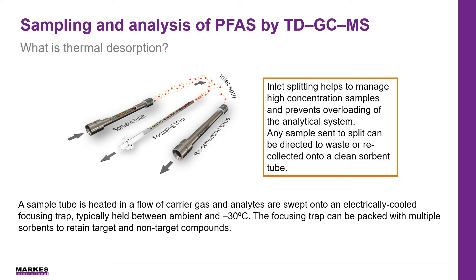For those of you unfamiliar with thermal desorption, let me quickly explain the process. Sample tubes are placed into the thermal desorber and leak checked prior to being heated in a flow of inert carrier gas. This releases the retained compounds and transfers them onto a narrow electrically cooled focusing trap. During this process a portion of the sample can be split and recollected onto a clean adsorbent tube, which can be used to store a precious sample, to validate the methodology, or to ensure efficiency of the method such as the complete desorption of the tube. This really is key to ensure good practice, validate the results and ensure robust methodology.